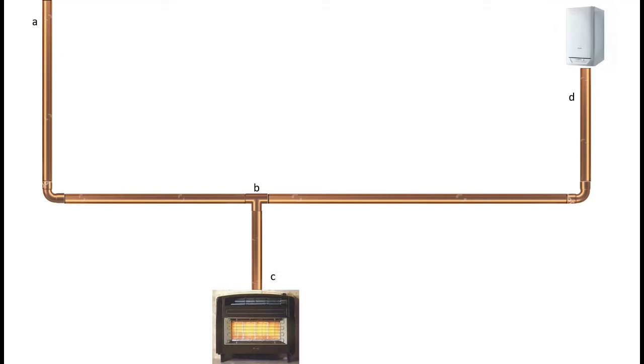We know from the previous lectures that we need to know how many meters cubed per hour the appliances demand. In this case, the boiler is 2 meters cubed per hour and the fire is 0.75 meters cubed per hour. That's the amount of gas they need to be able to operate properly. So we know that A to B needs to supply 2.75 meters cubed per hour.